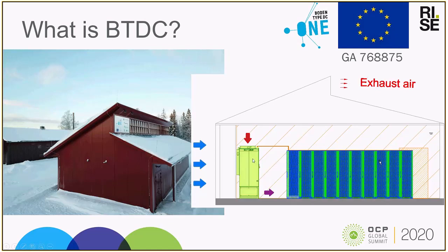So the cold aisle is contained. There are eco-cooling direct fresh air units towards the left here, which is on the left side of the building. And this takes air from the outside, and then the hot air that is injected into the whole data center room here is either returned to the coolers and mixed with the outside air, or exhausted out of the building. So this is the configuration we have in Boden.